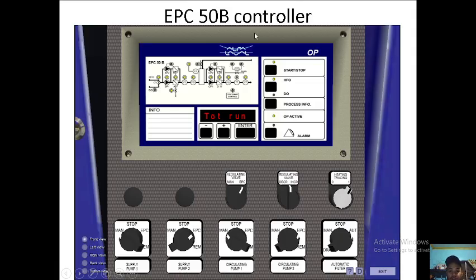So this is the EPC50B controller. We can push this to start or stop the system. We can change over from HFO to DO, and here information will be displayed. And here, if there is an alarm, you can push this one so that you can acknowledge the alarm. We have here the total running hours. You can choose yes or no in here, enter, and here we can use the manual mode or the EPC or the automatic mode. For the regulating valve, we can decrease or increase the regulating valve.